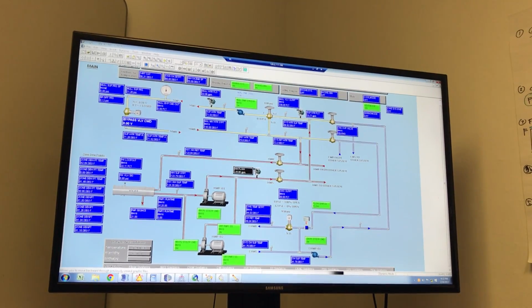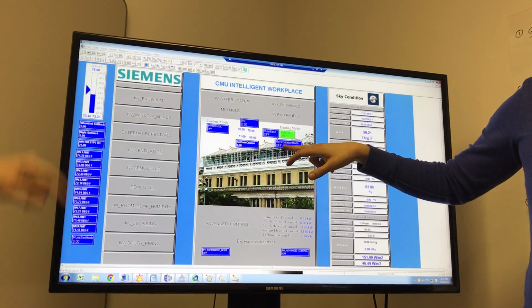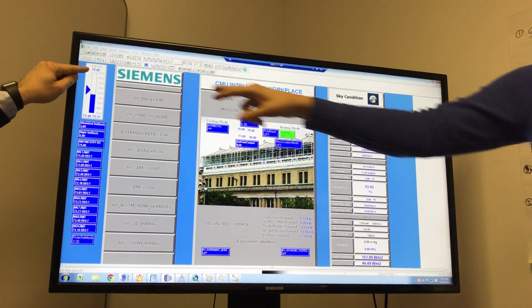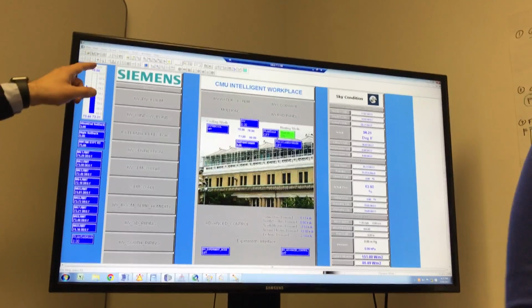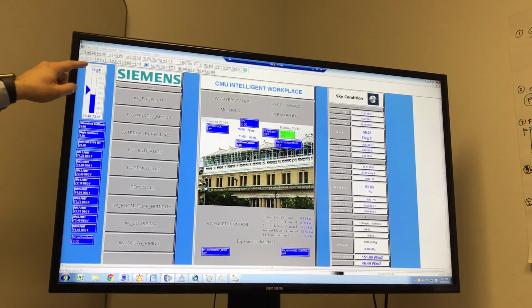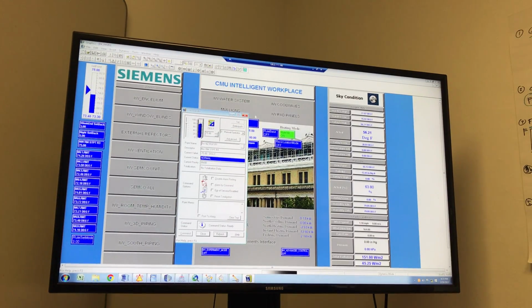I didn't see where you changed that. My set point was 71, then we measured 73, so the system was in recirculation, everything is happy, I'm just recirculating the water. But then I fake it and say now 75. Where did you do that change? I just click on this, change the value, and you command. You did it once in this field and once in another field, because the other one was the code I just removed. I see, so I'm cleaning the values right now.